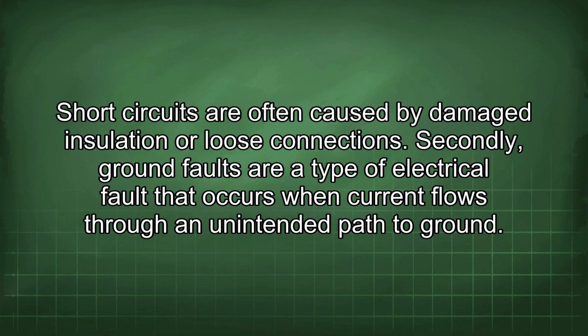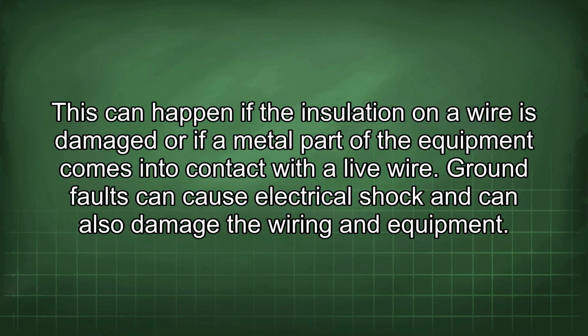Secondly, ground faults are a type of electrical fault that occurs when current flows through an unintended path to ground. This can happen if the insulation on a wire is damaged or if a metal part of the equipment comes into contact with a live wire. Ground faults can cause electrical shock and can also damage the wiring and equipment.